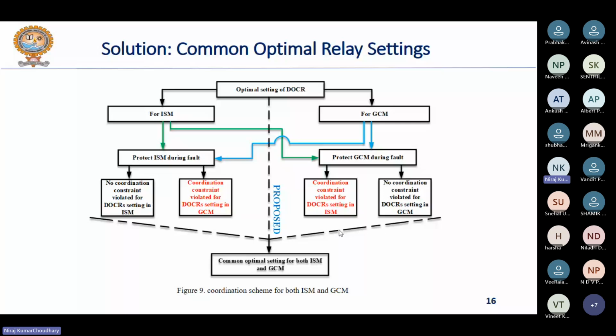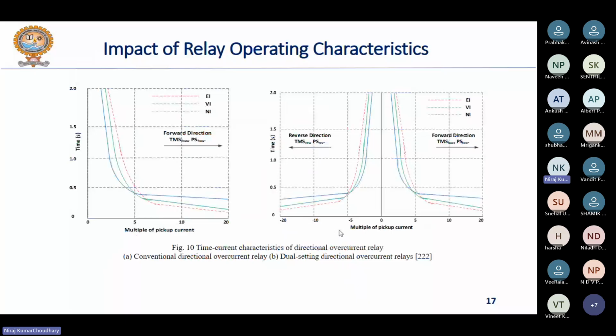Now, after the mode of operation of the microgrid, the performance of the protection coordination scheme also depends upon the different types of relays as well as their characteristics, right? I will show you in this slide the two basic characteristics. First one is the standard characteristics. Here you can see the standard relay characteristics as per the IEC 60255 standard. The three characteristics are normally inverse, that is NI, then very inverse, then the third one is extremely inverse.